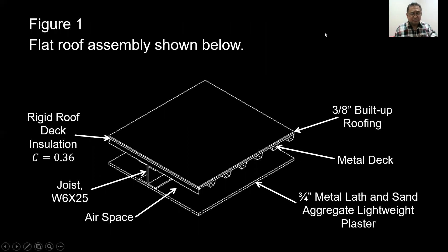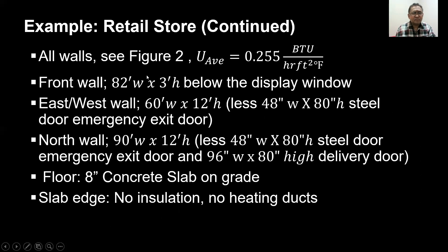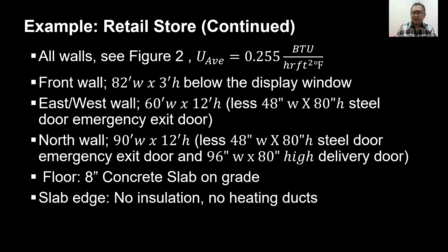This figure shows the roof assembly. You have a rigid roof deck with insulation having a C value of 0.36. You have a joist made of a W6 by 25, an airspace, a metal lath and sand aggregate lightweight plaster, a metal deck, and a 3/8 inch built-up roofing. All walls as shown in figure two in the next succeeding slides will have a U average of 0.255 BTU per hour square foot degree Fahrenheit.